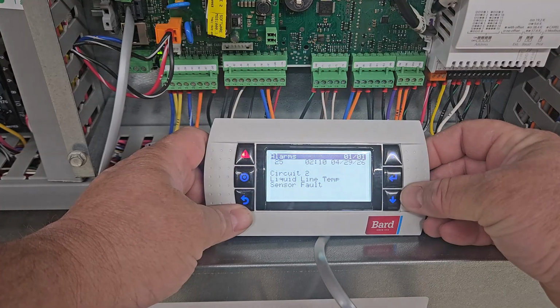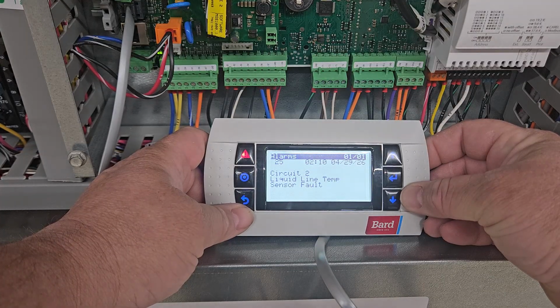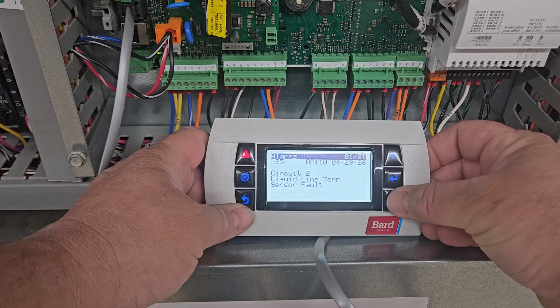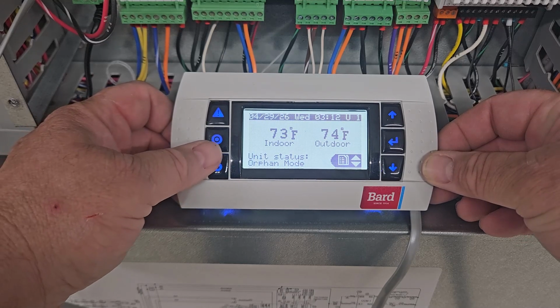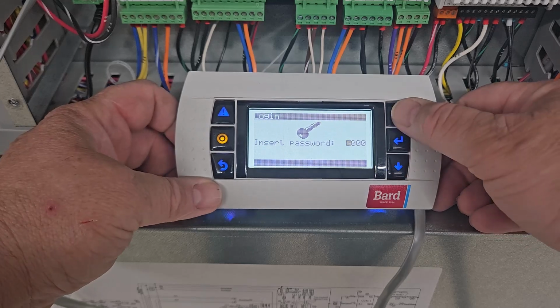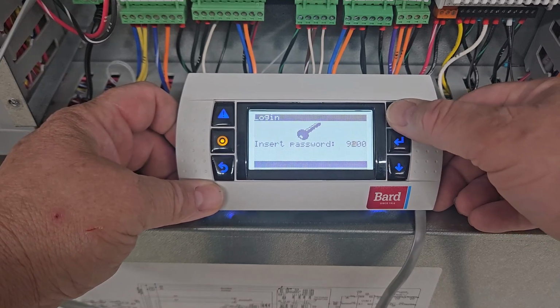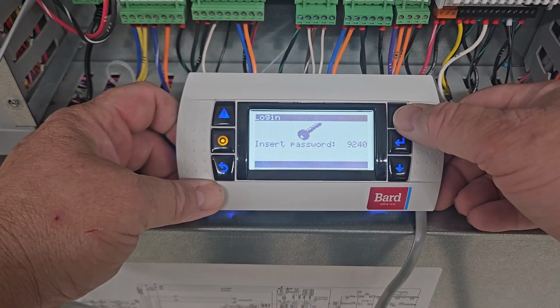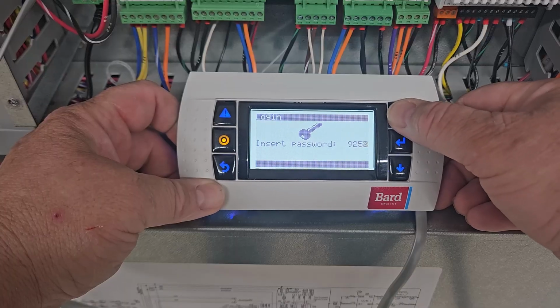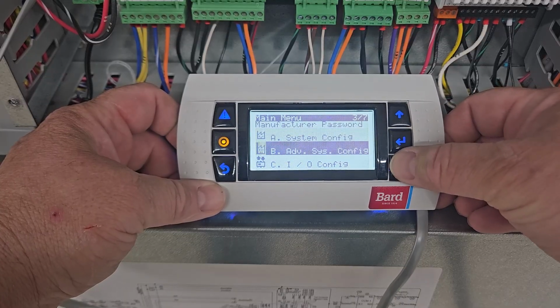With the TEC-EYE or PGD display, check the unit for any alarms. I had an alarm because I pulled a wire off of the PLC while I was removing the wires to the blower assembly. After fixing any alarms, clear the alarms and navigate to the Installer Setup menu. Enter in your engineering password and find the I/O configuration menu.